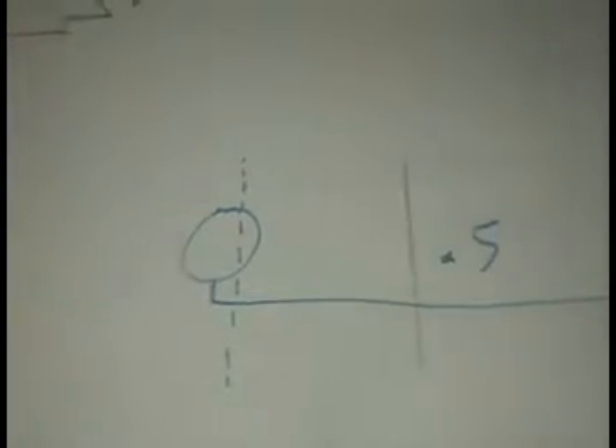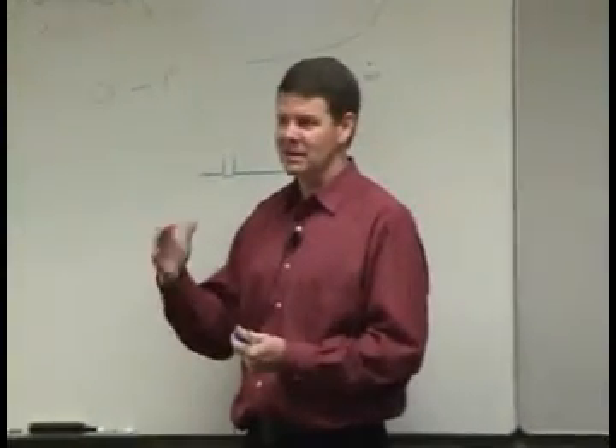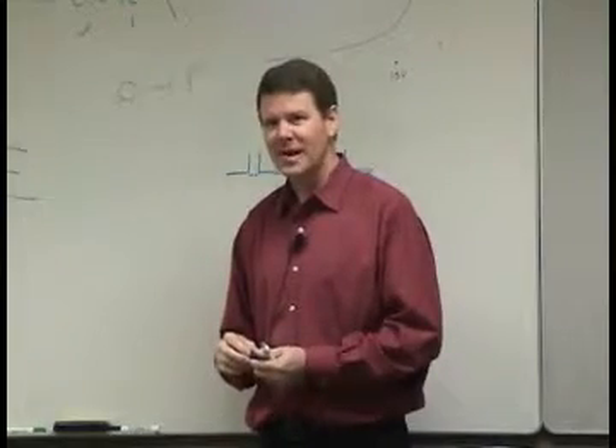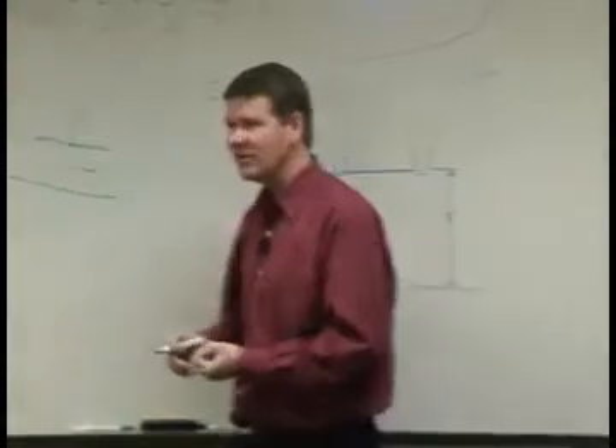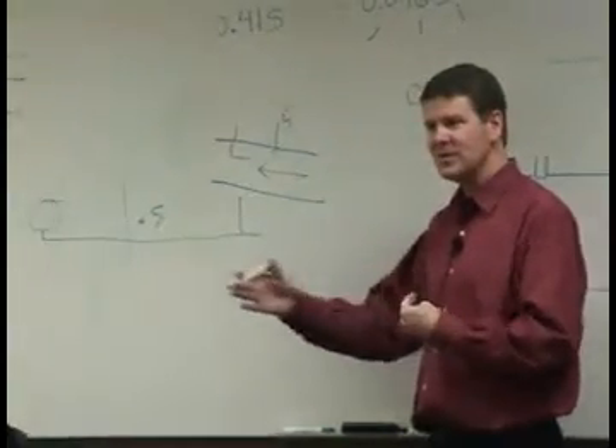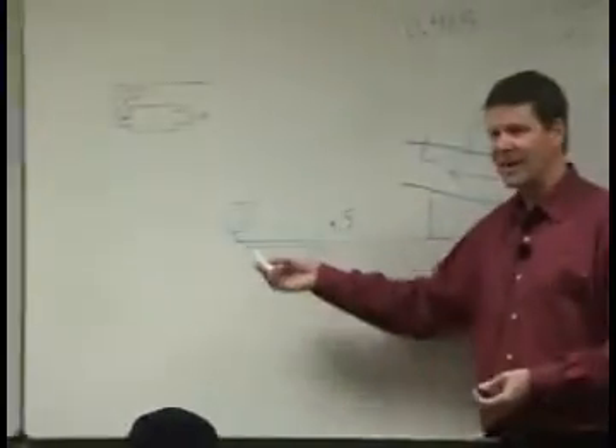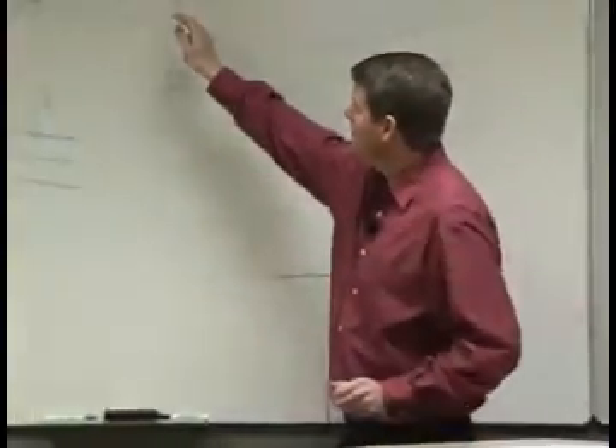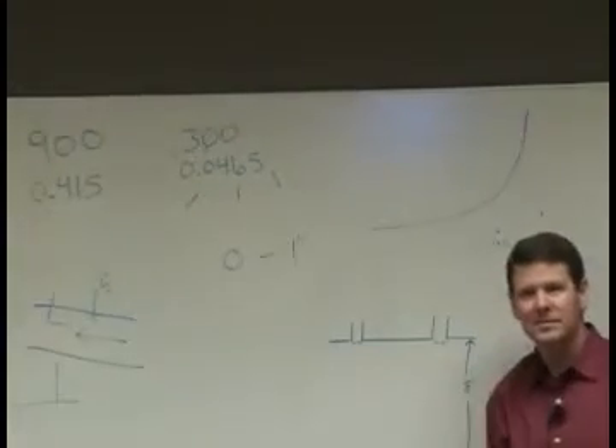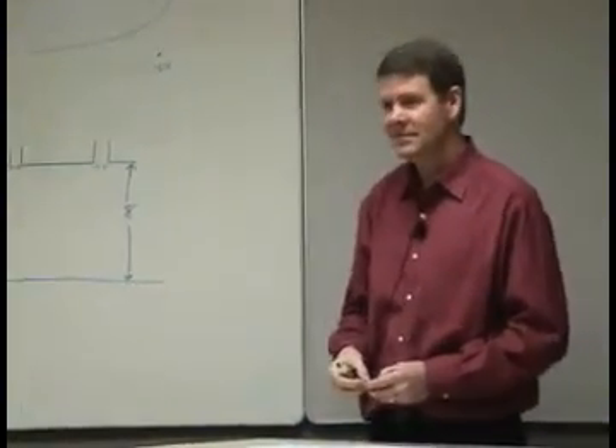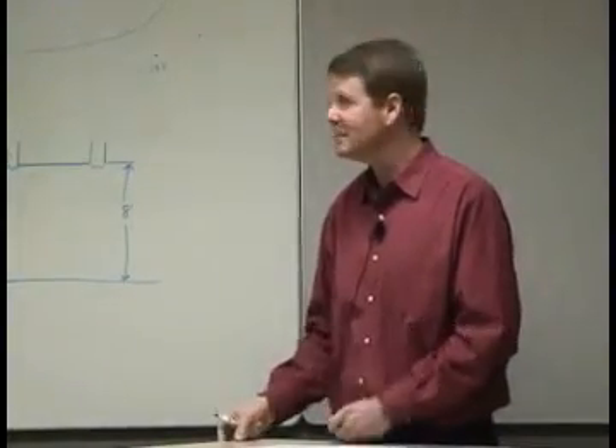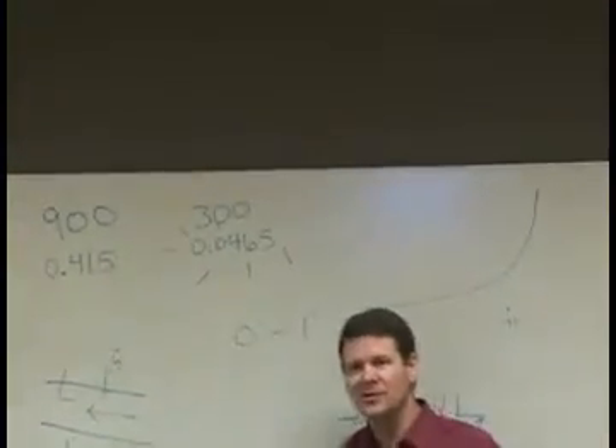In the old days of mechanical controls, like a pressure gauge with an old Bourdon tube in there that flexed as you put pressure on it, the most accurate place in the range is going to be out there in the middle. I've heard two-thirds is the most accurate place. Electronic doesn't suffer from that same problem. You get a lot better accuracy through the whole range. But if you're trying to measure that close to 0, at the bottom end of your scale, you're in huge trouble. So if this thing is jumping in 0.01 jumps, even 0.008, that calculates out to be quite a few CFM.